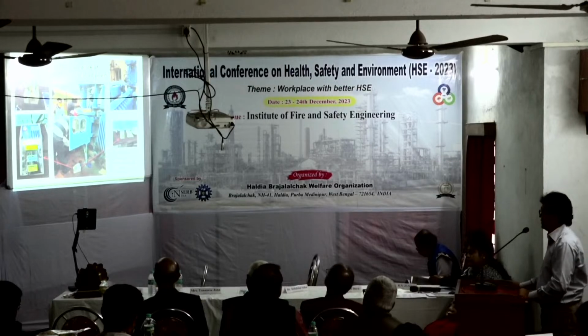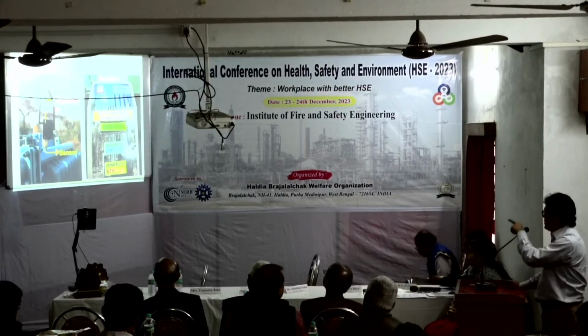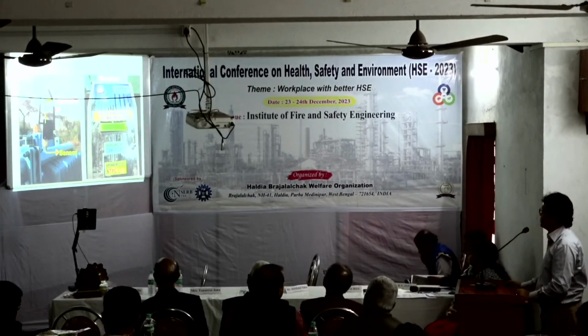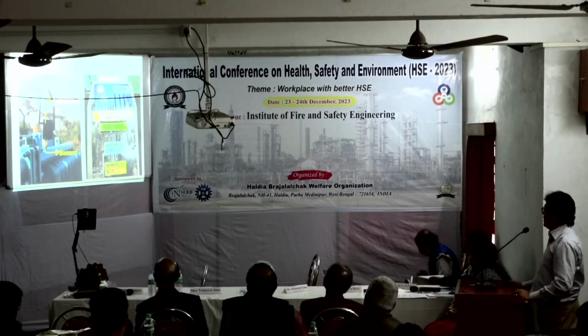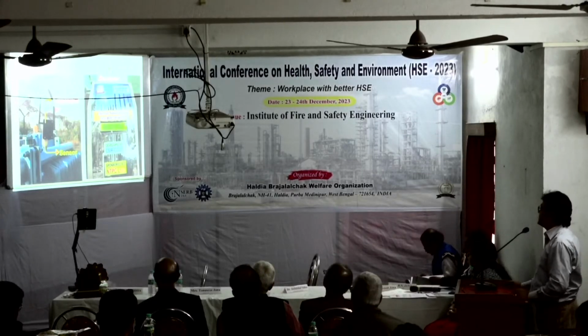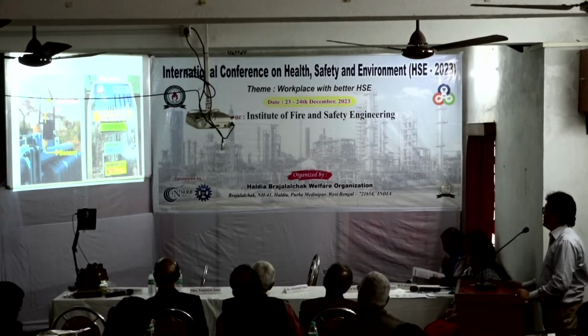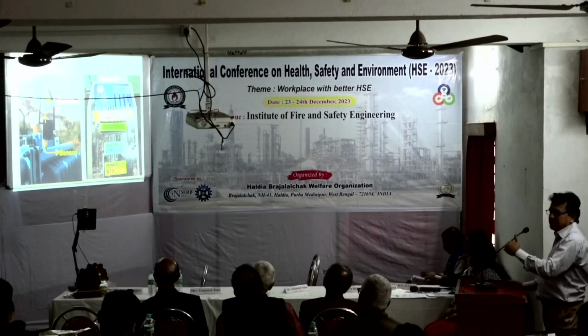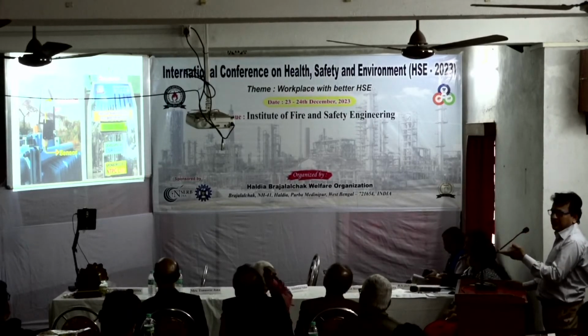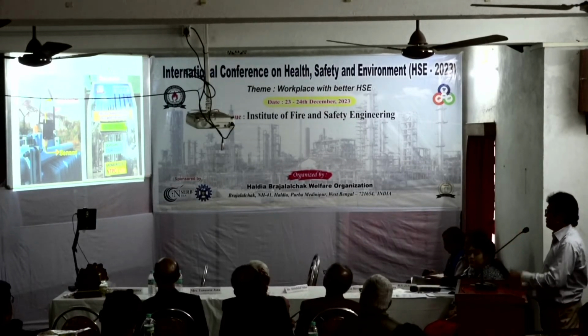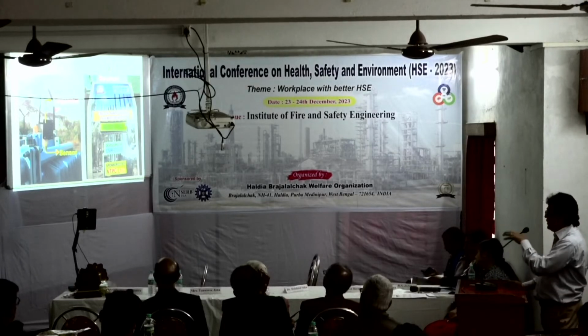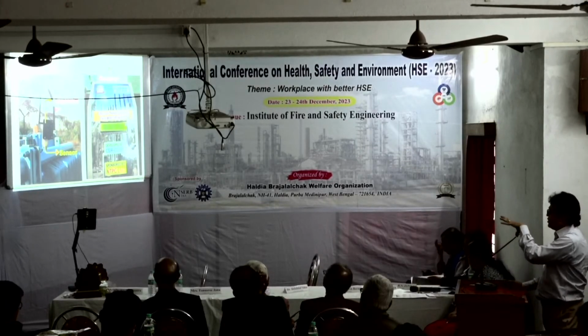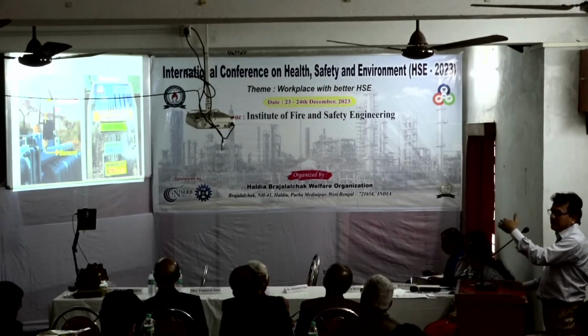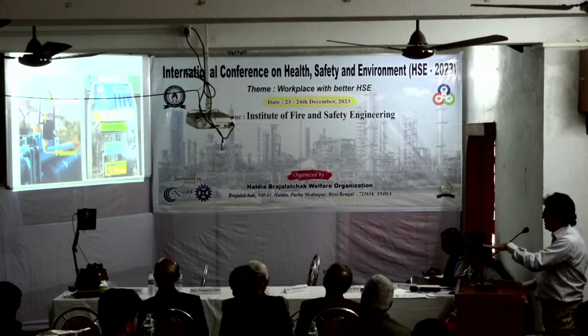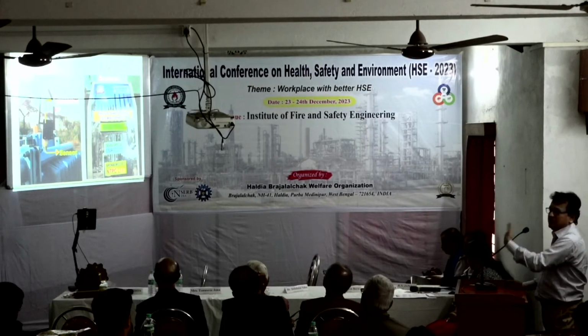This is a Faridabad plant. These are the meters; initially 3 sensors were installed. The 9A shows 26 ppm, and the 9B shows 5 ppm, so their limitations are there. There are 2 types of transformer, step down and step up; this is the step down transformer. According to the measured moisture, if the moisture contains beyond their limit, then the transformer is stopped and the oil is recycled.